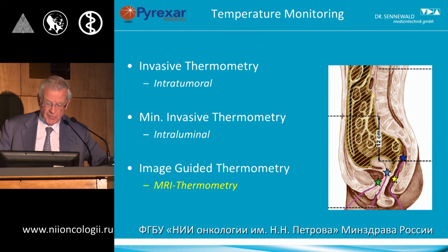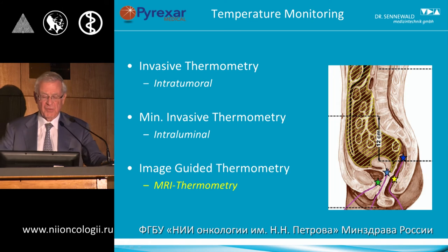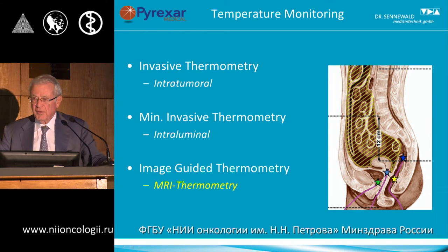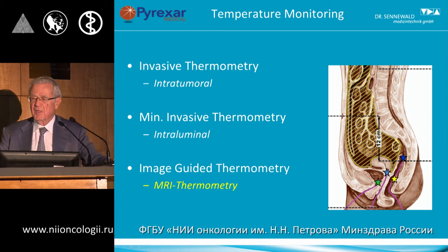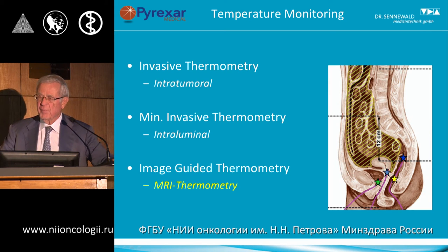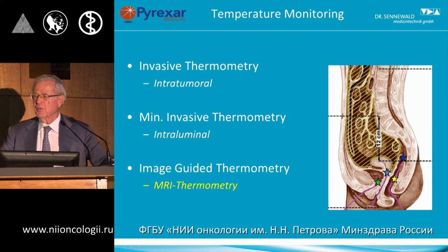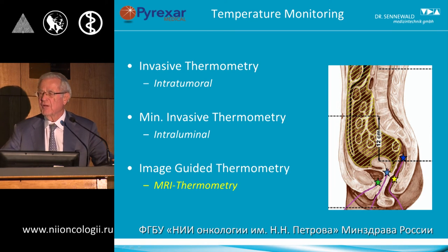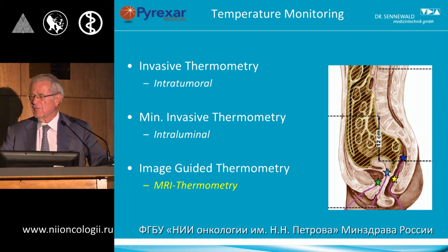Coming to temperature monitoring: the standard monitoring mode is invasive — transcutaneously intratumoral — where a catheter is placed transcutaneously inside the tumor. Inside this catheter is a thermistor, which can be varied to see more than one temperature point. This shows how limited such a mode is, as you cannot get more than a handful of temperature points within one catheter.